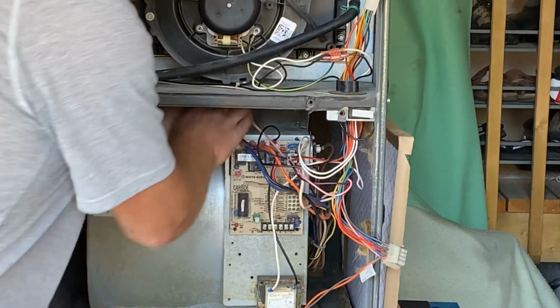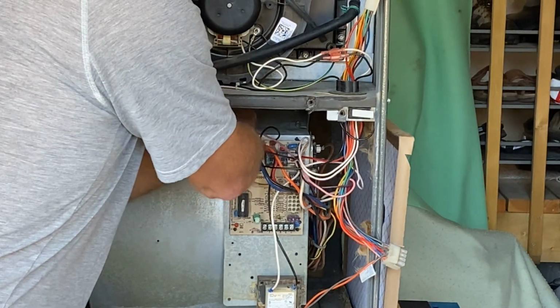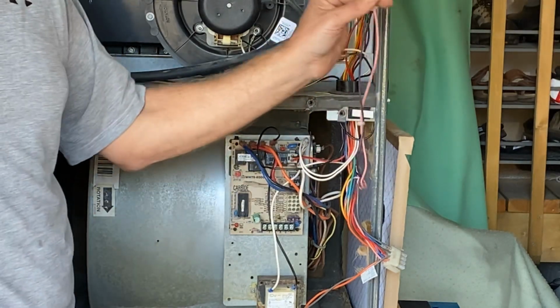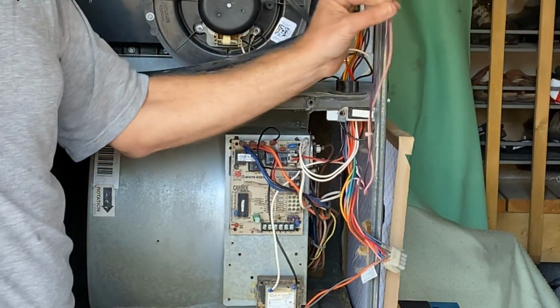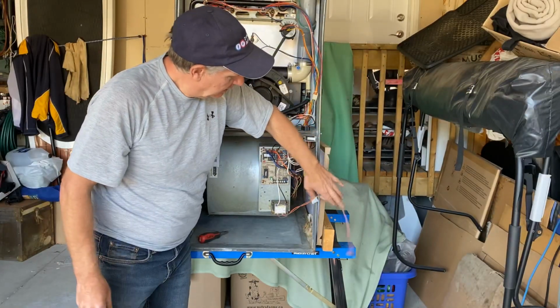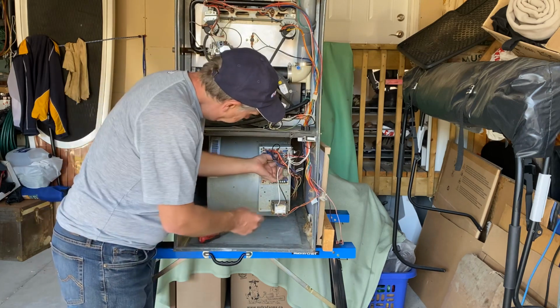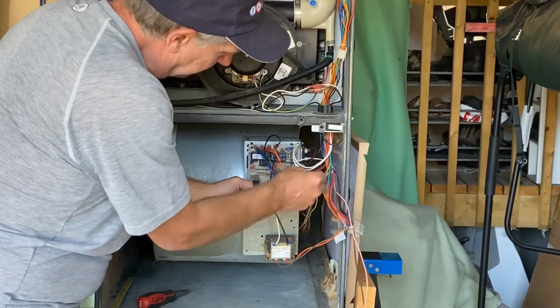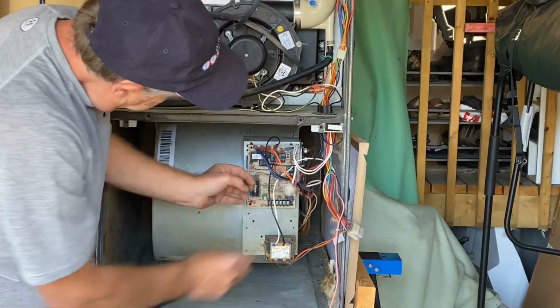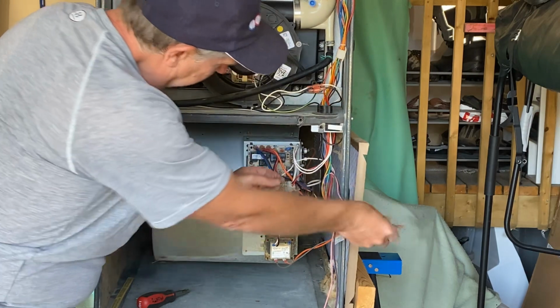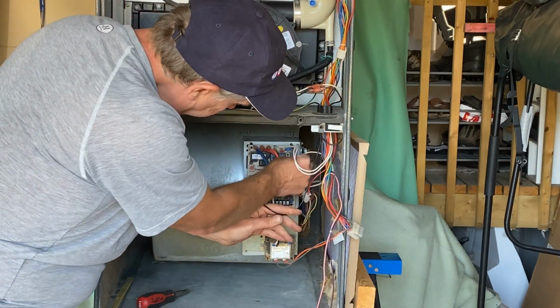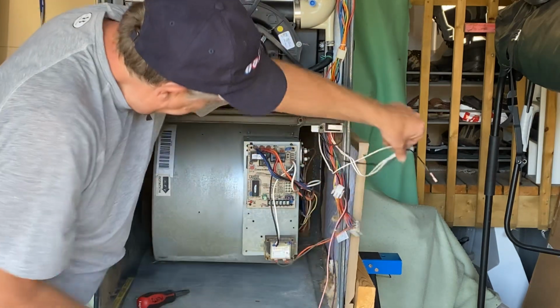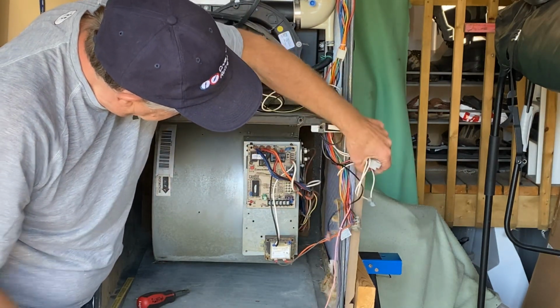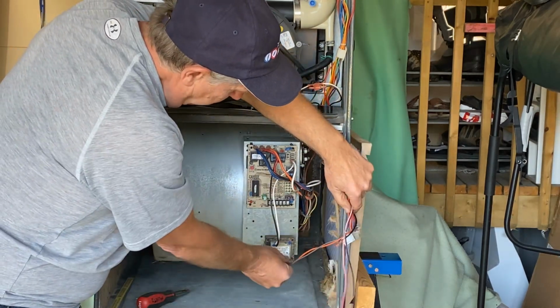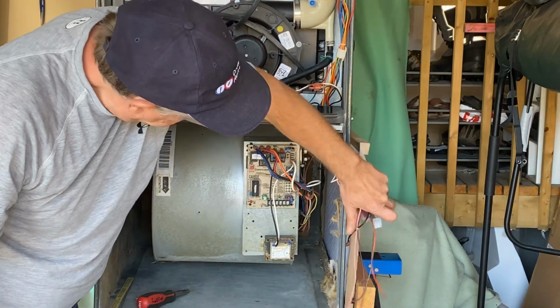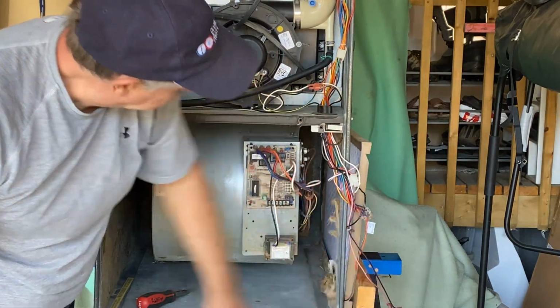I don't think these 2 wires, the limit switch wires, are going to be in the way. This limit switch, the whole thing, I mentioned there was a limit switch down here, it just snapped into place. It's in the way for the blower to come out, so it has to actually be taken out and put out of the way. Power wires, red and black right there, just take them off. This black wire has to come off, and these neutral white wires need to come off. Now, my transformer wires - I think that once I take these transformer wires off, my blower should be free and clear to come out.